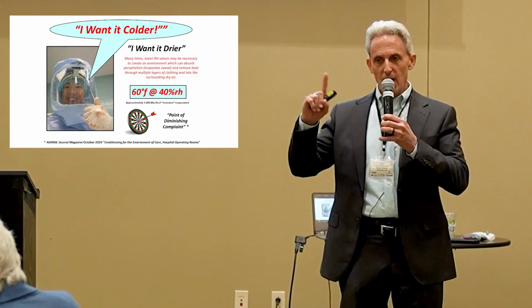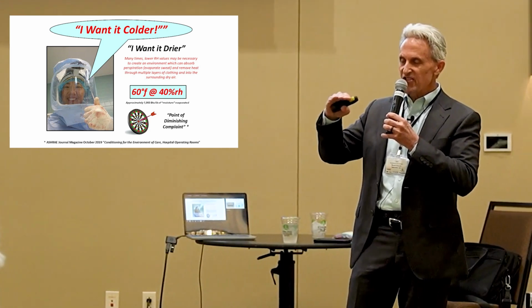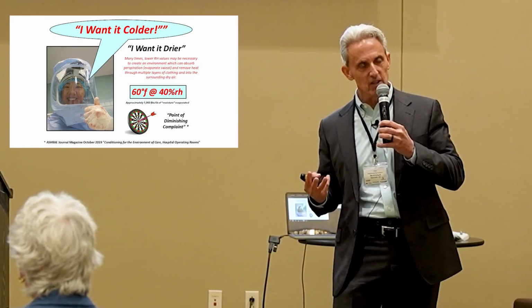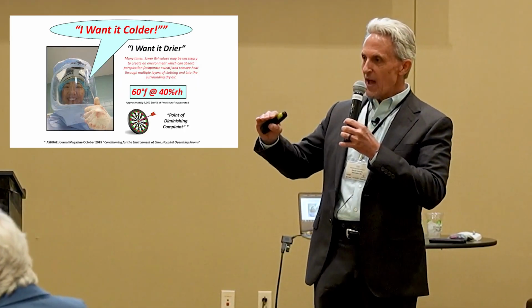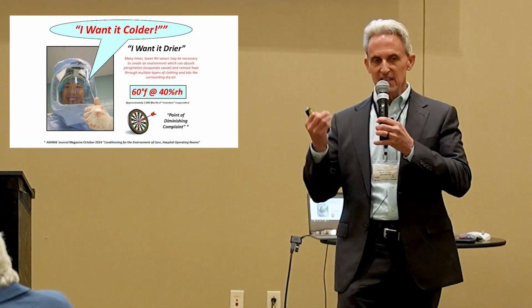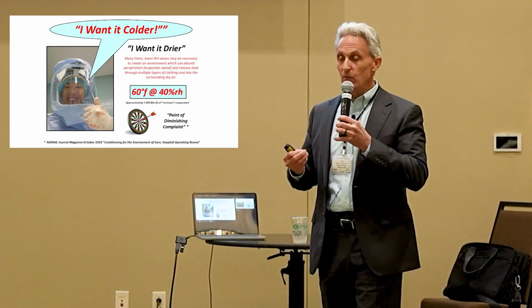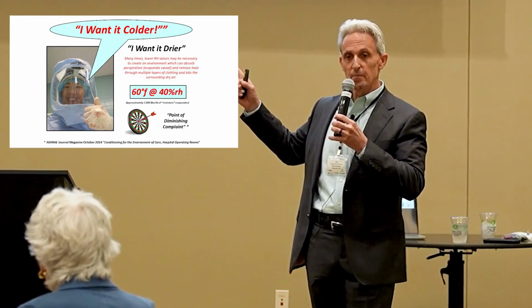And for every 1 pound of sweat that evaporates from the surface of our skin, we remove 1,000 BTUs of heat from our body. It's not just temperature, it's evaporation. And if we can't evaporate the sweat from the surface of our skin into the air that surrounds us, we cannot maintain comfort, we will be uncomfortable, we will be hot, and we may actually enter levels of heat stress, and this happens to surgeons all the time.